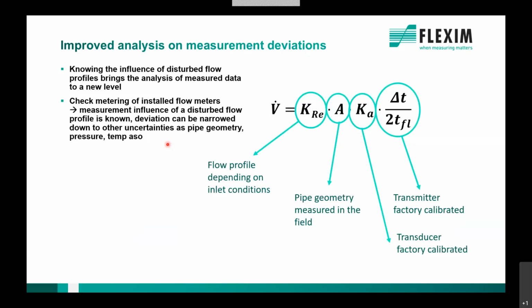Knowing the flow profile tells us that everything which is left in uncertainty or as an error must come from the pipe geometry or build-ups or things like that. Or it points out that the meter you compare with is probably wrong. That's what you basically can do. Before, it was always difficult to say, well, maybe the build-up is the problem why we are measuring off. We don't know what the influence of the disturbance is. Since we know the disturbance, we can eliminate that factor and bring down the problem to the real influence, what we see on site.